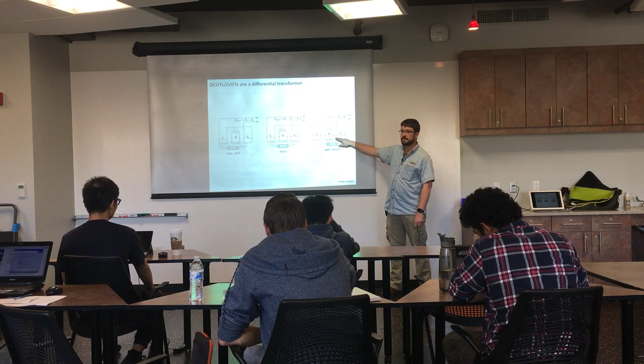This is what that looks like if we look at the output of the transducer: all the way to the left, all the way to the right, and the null. If you hooked a voltmeter up across the secondary windings, you'd see this symmetric V-shaped curve. Notice how out here it's not linear, that's because it's beyond the end of the range, so we won't use that, stay away from the ends of the transducer. We've got two nice linear lines here, and then possibly a little bit of offset.